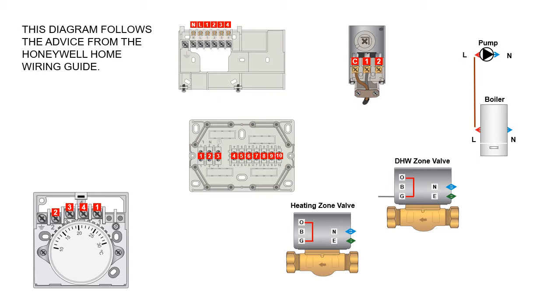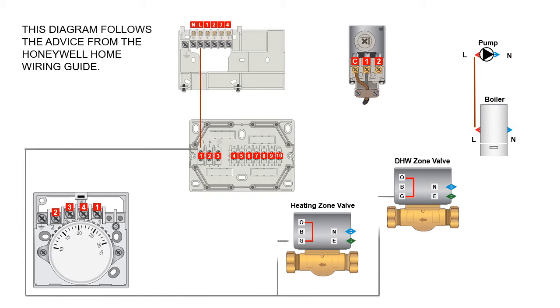First of all — from the fused spur — it's a good idea to wire in your permanent lives to the programmer, and also the two gray wires from your two zone valves: your heating zone valve and your domestic hot water zone valve. The gray wires are permanent lives and should be wired into terminal one.